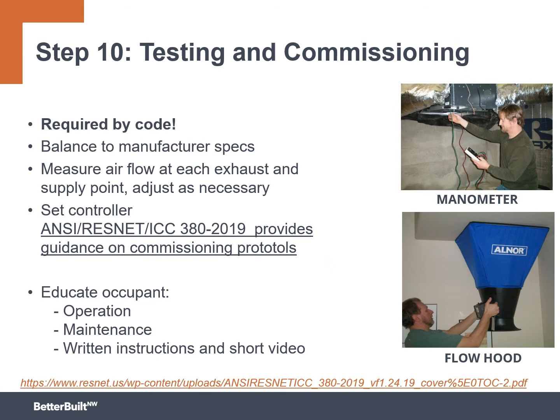The final required step to doing this is the testing and commissioning of these systems. This is required by code. Some jurisdictions may even mandate that a third party do this. So in other words, not the installing contractor. So be very aware of what your local jurisdiction requires, but this is required by code. You need to make sure that the system is balanced to its manufacturer's specifications. You measure the airflow at all the exhaust and supply points and then make some adjustments as necessary.